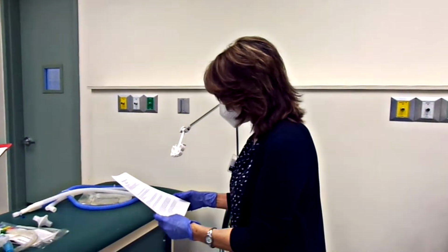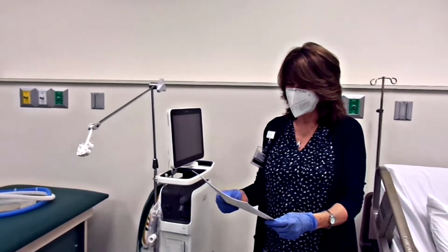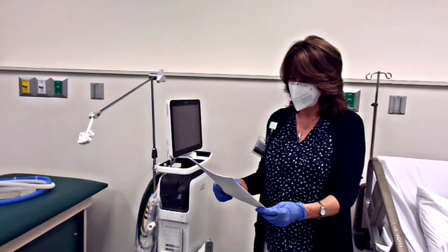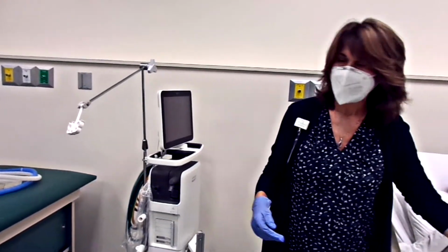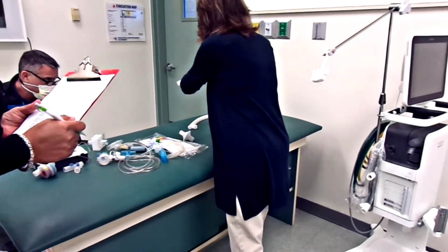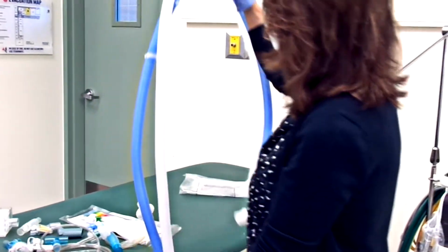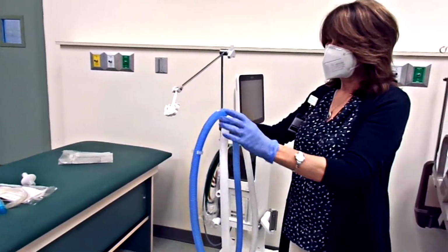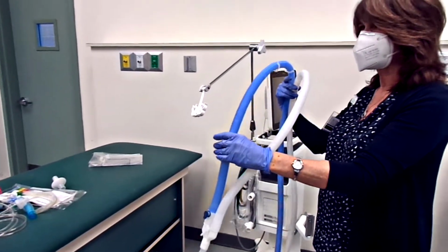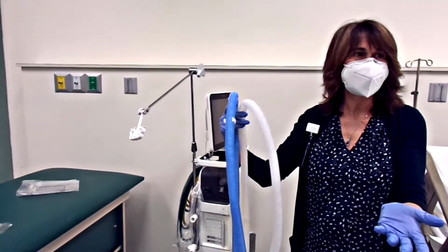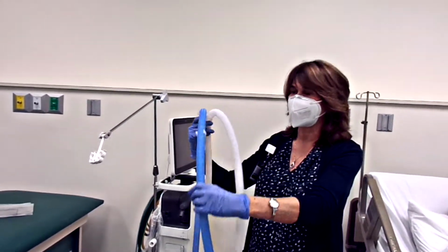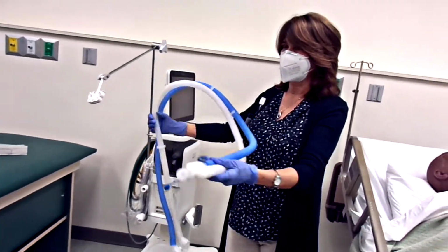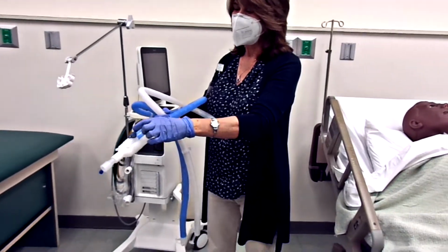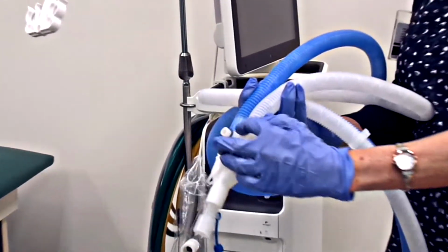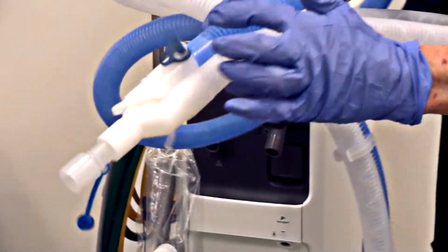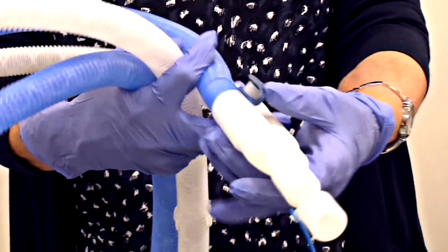Inspiratory limb tubing. The inspiratory side of the circuit brings a fresh flow of gas from the ventilator to the patient. Identify the inspiratory side by locating the temperature sensing port. Okay, so when you're putting a circuit on a critical care ventilator, it'll have 2 tubings, the inspiratory tubing and the expiratory tubing. So here the inspiratory tubing is blue, but you can't always count on colors, because if they switch manufacturers, it could be different colors. The inspiratory could be clear. So how are you supposed to know the difference between the 2 tubings? The port. Yeah, you look for the temperature sensing port, and you're always going to be sensing temperature on the inspiratory side. So wherever this is located, that's your inspiratory tubing.